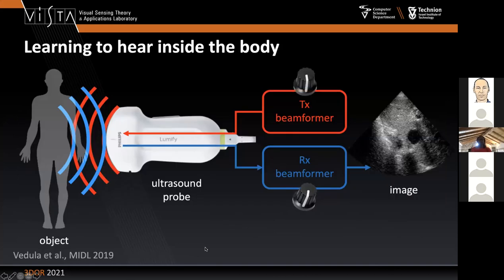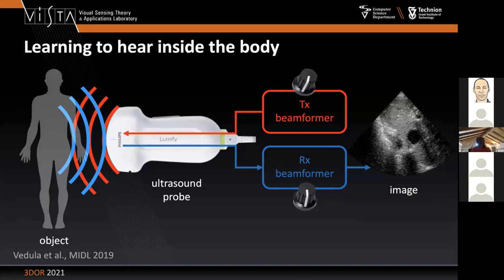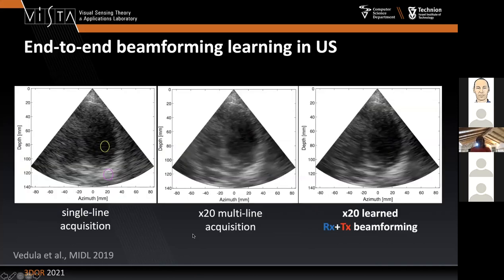What is more interesting is to learn the transmission as well. When we learn the transmission together with the received beam former, we see patterns that don't look like focused beams — not even like beams at all. This is something you would never probably configure your machine to transmit, but in concert with the learned beam former, the machine produces better images with smaller artifacts. You can roughly increase the acquisition speed by a factor of three with comparable image quality.